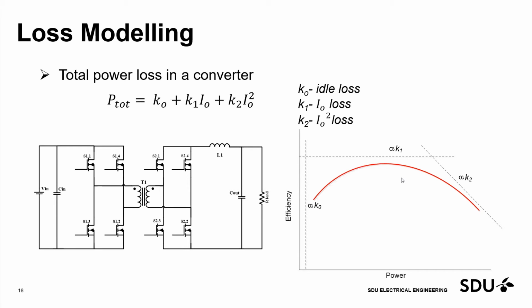So by looking at the efficiency curve, we can see how the person has designed the converter. Sometimes it also depends on the application, because in some applications you only work at 40% load, and the remaining load range occurs only once in a while. So you have to really think about where you need your efficiency curve to peak.